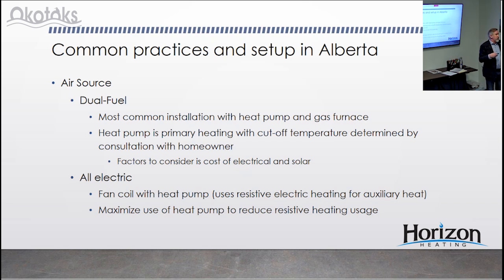So there are also all electric air source heat pumps. That's a heat pump paired up with an electric furnace. They're not called electric furnaces, they're called fan coils, but think of it as a furnace with an electric backup in it. In that case, we would actually want to use the heat pump all the way down to its design temperature, all the way down to -30 or -20 or whatever that heat pump would run to, because it's going to be more efficient than the all electric system or the electric resistive backup that comes on all the time. But there's going to be times when the heat pump won't heat your home, whether it's frozen solid because it's cold outside, or there's a snowstorm, or it's so cold that it needs to go into defrost mode, or all sorts of different factors. And what happens is the electric backup comes on in conjunction with the heat pump at the same time and bumps up the temperature, and the heat pump just keeps cruising along.